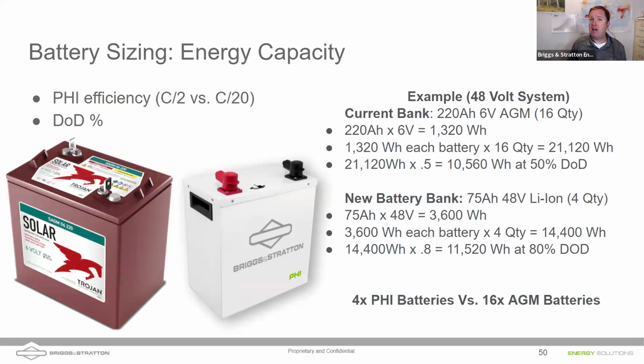With lead acid batteries, we really only want to have a 50% depth of discharge. Remember, I talked earlier about ours having an 80%. Lead acid batteries, usually this amp hour rating is at a 20-hour rate, whereas we can actually do it at a 2-hour rate. Well, actually, the amp hour rating is good no matter the rate. It's the energy capacity that's affected by your rate of discharge.